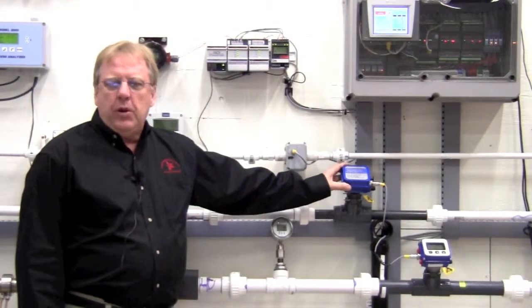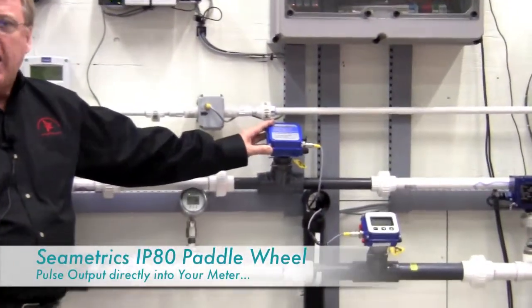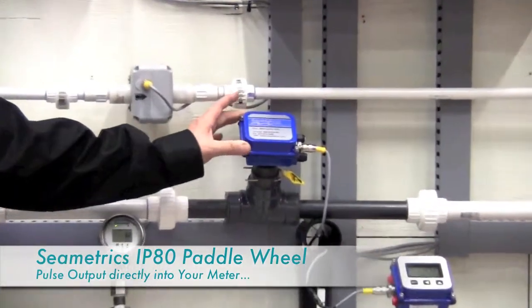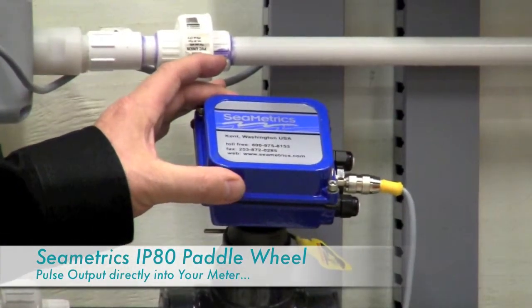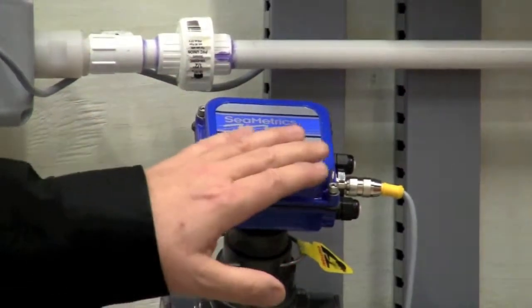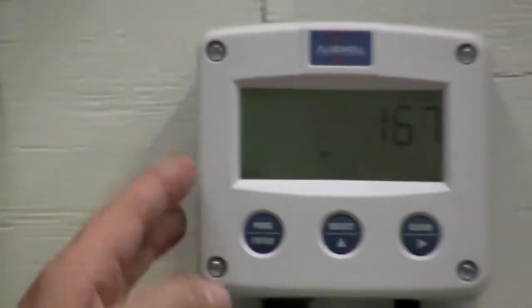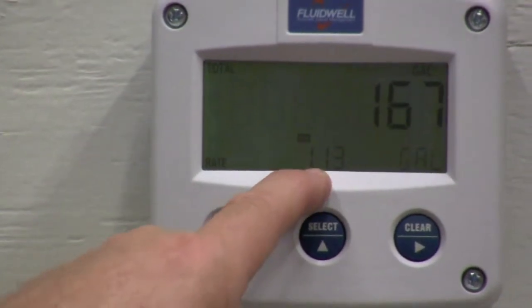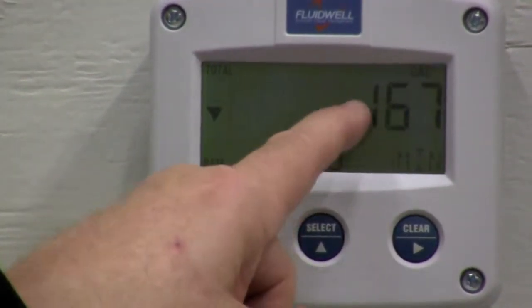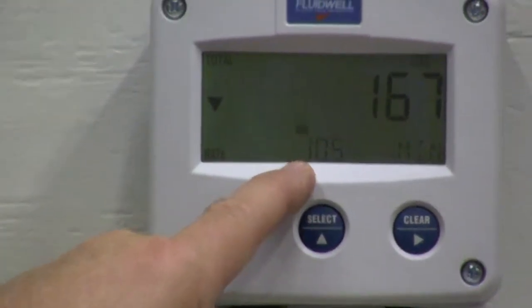We also have installed in one of our one-inch lines a Seametrics insertion paddle wheel flow meter. This meter has a blind unit with no display, and we're taking the pulse output from this meter up to our Fluidwell display mounted on the wall here. You can see our gallon per minute reading which is 11.3, and the top display will be your totalizer that will count in gallons for you.